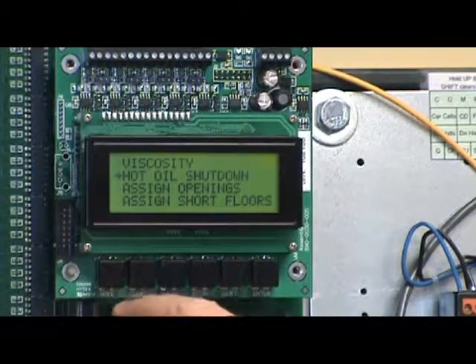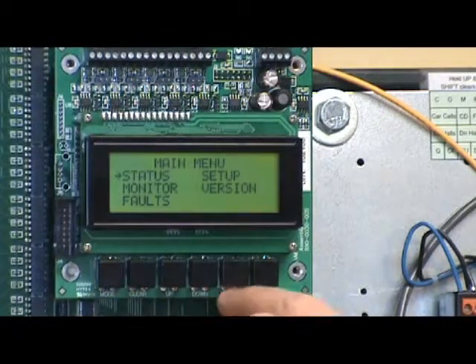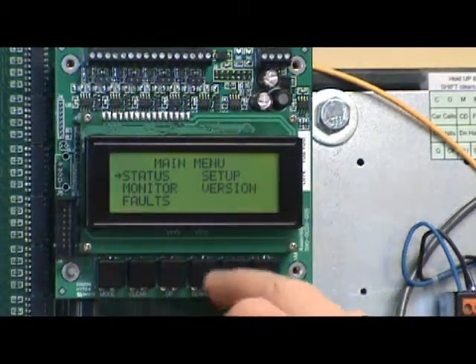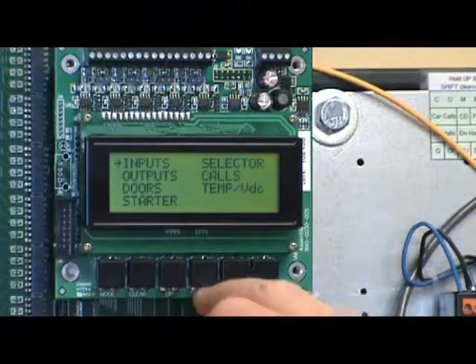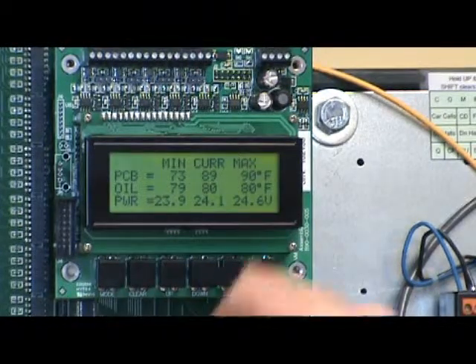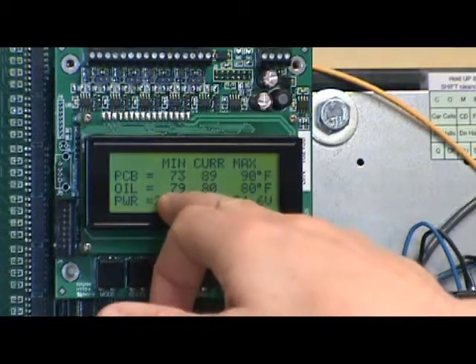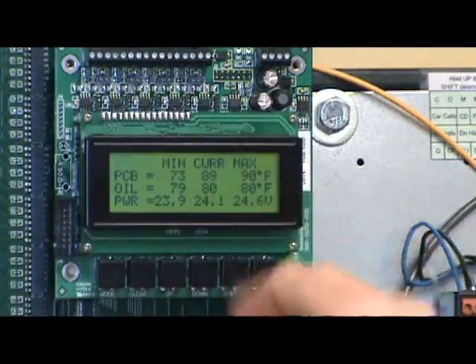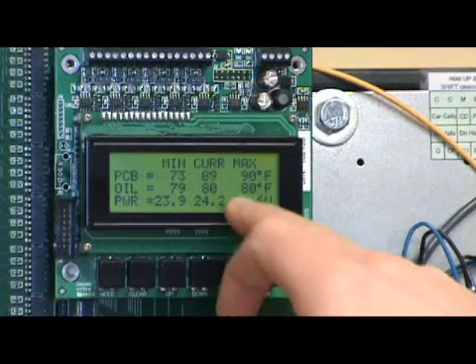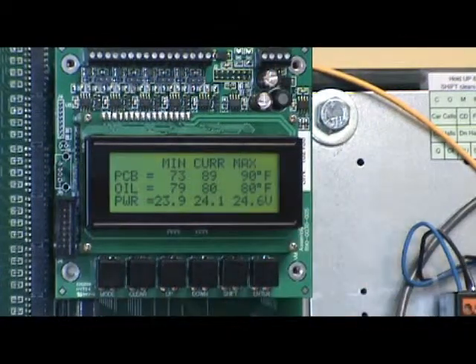A couple other things I want to show you here. If you go back to the main menu screen and you go to monitor, now that you have a temp sensor hooked up, you're going to be able to view the temperature of the oil right in the monitor. It'll give you the minimum temperature and the maximum temperature since the power has been turned on, and then your current temperature. So it's kind of just a slick way to look at the quick temperature on the oil.